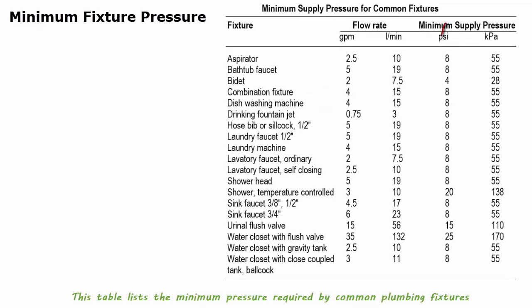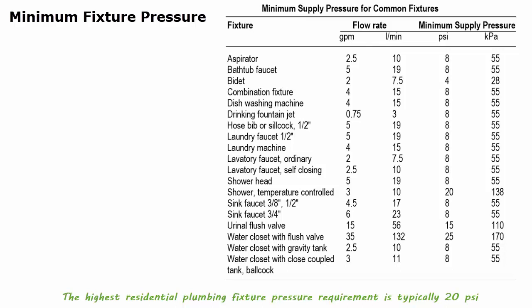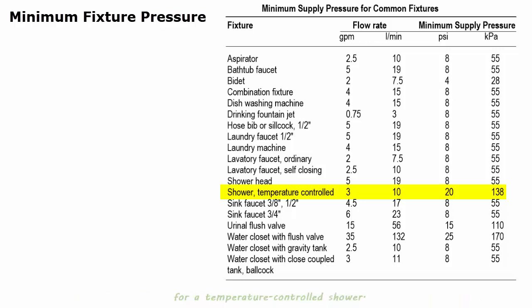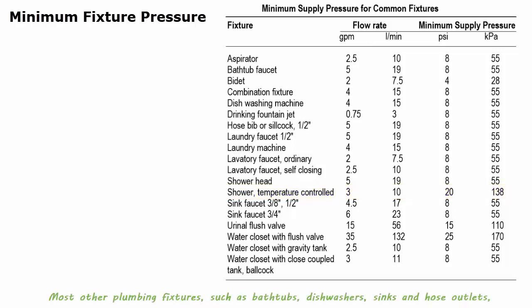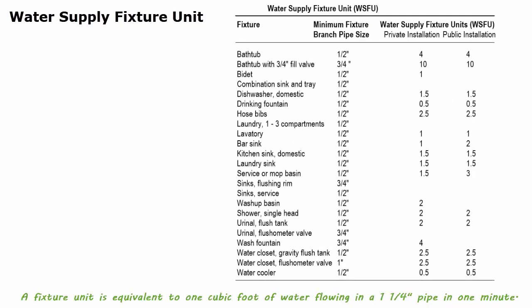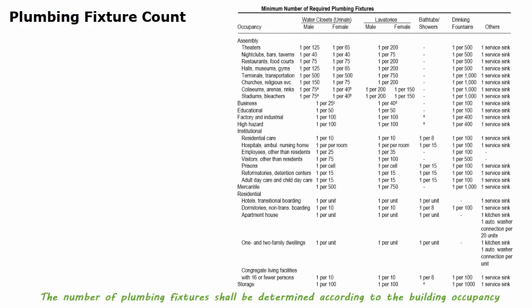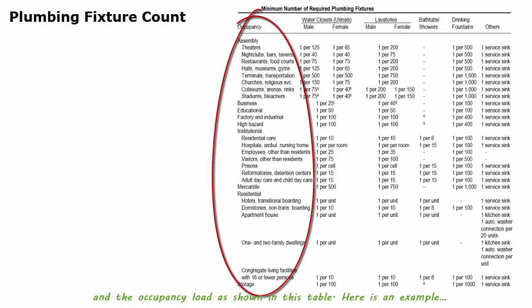This table lists the minimum pressure required by common plumbing fixtures for them to work properly. The highest residential plumbing fixture pressure requirement is typically 20 psi for a temperature-controlled shower. Most other plumbing fixtures, such as bathtubs, dishwashers, sinks, and hose outlets, require a pressure of 8 psi. A fixture unit is equivalent to one cubic foot of water flowing in a 1¼-inch pipe in one minute, and is used for sizing both water supply and wastewater pipes. Different fixtures are rated for different fixture units based on the flow rate they require.